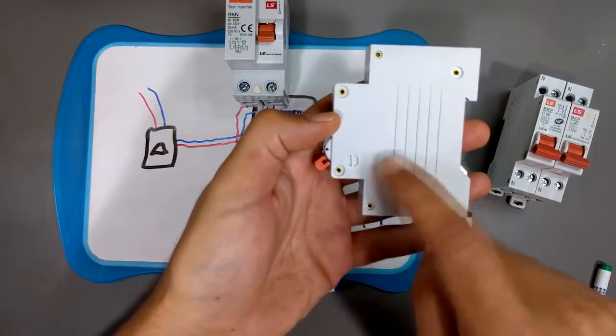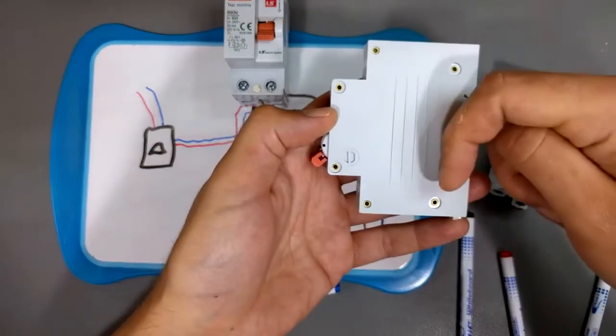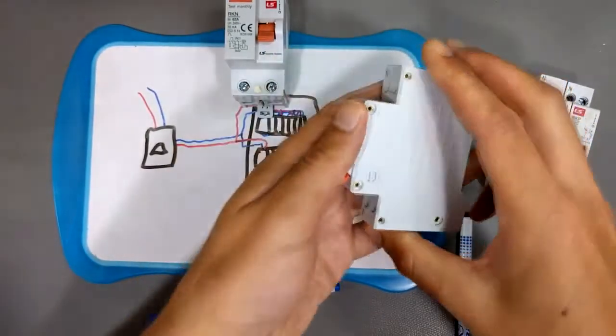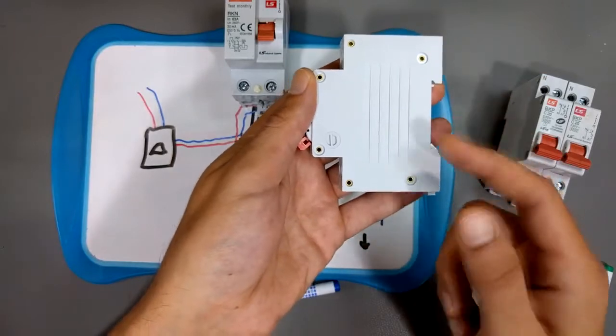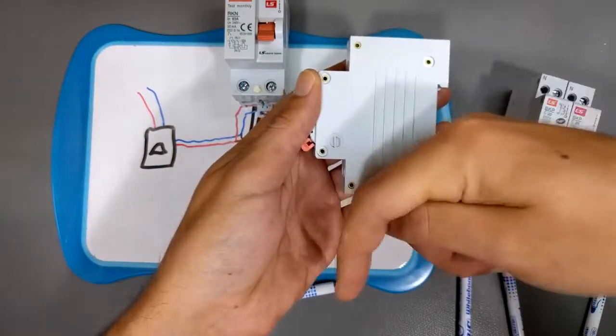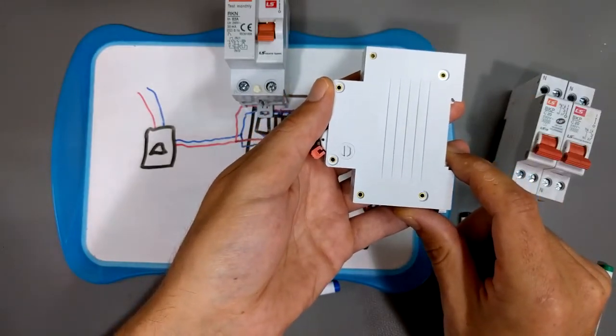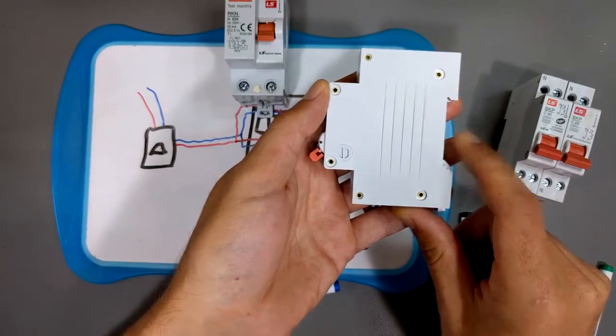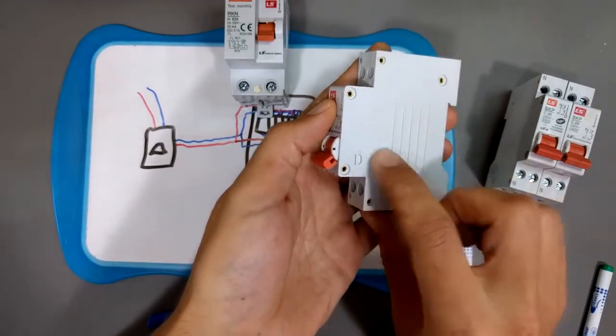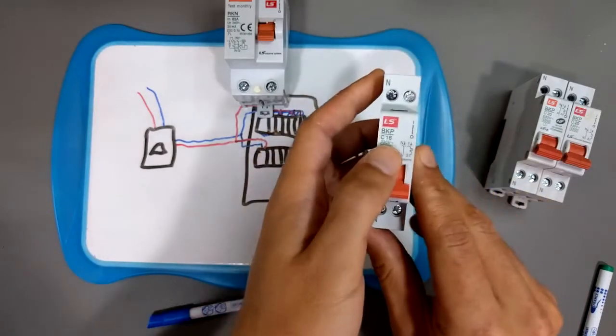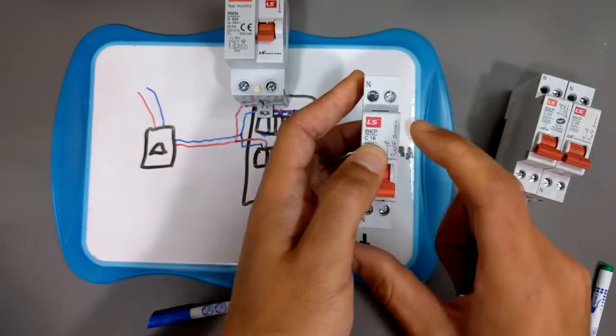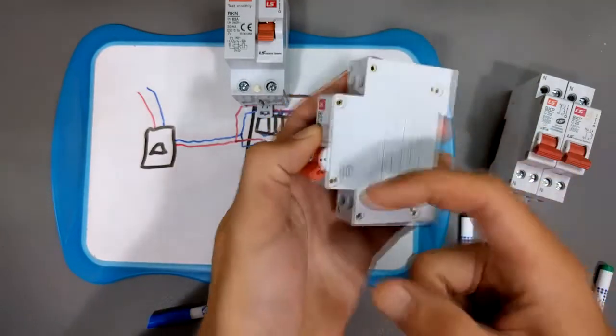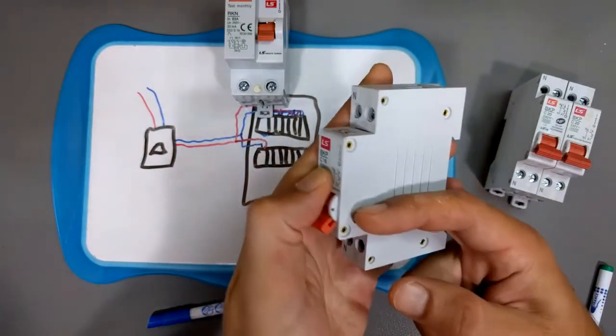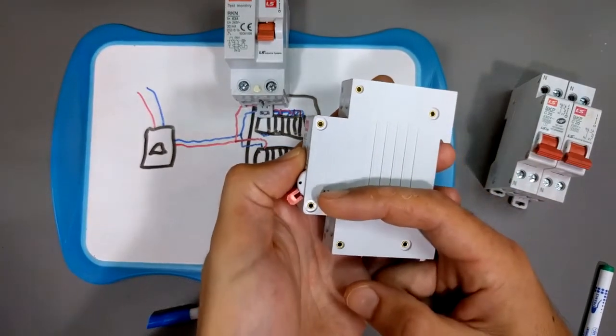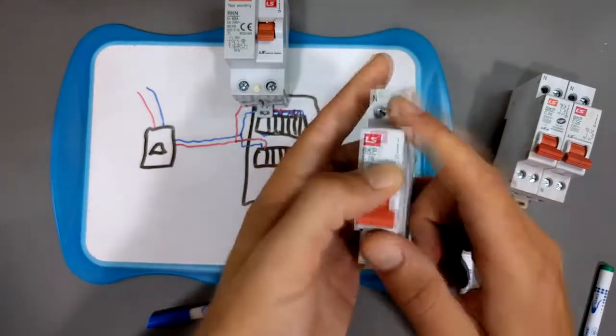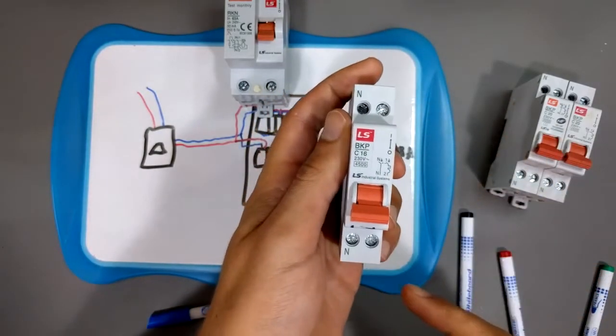That's the magnetic aspect of the protection. Very large current goes in, trips the mechanism, flips it off. The second part is usually a bimetallic strip, which I'll put a link in the description, and you can watch my video on how an electric tea kettle turns off, because that explains bimetallic strips. The same thing is used in here, and the bimetallic strip is the thermal part. This is rated at 16 amps. When 14 amps is flowing and then 15 amps, the bimetallic strip starts to heat up, and right when you hit about 16 amps, maybe slightly less or slightly more, the bimetallic strip bends enough to take your breaker and flip it off.